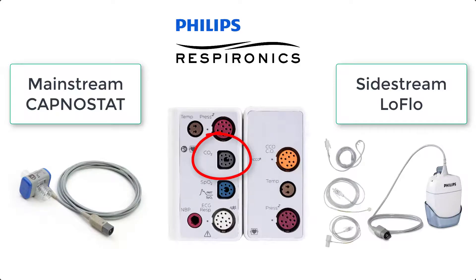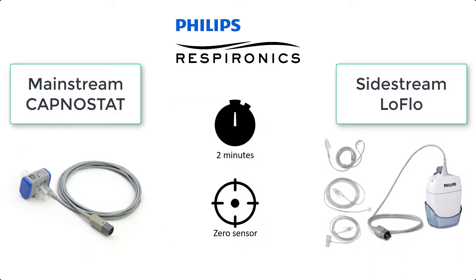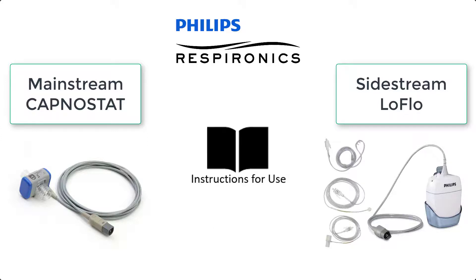Check if your monitor has the appropriate connector to use Mainstream Capnostat or Sidestream LoFlo from Philips Respironics. In both cases, when connecting the sensor cable, you need to wait 2 minutes for the sensor to reach its operating temperature, and you must zero the sensor by exposing it to room air before you can start monitoring. Read the instructions for use of your Intelliview patient monitor and contact your local Philips representative for further clinical advice.